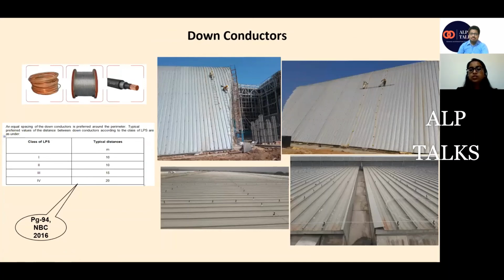Also, these holders and connectors are used at every 1 meter. If I am laying the down conductor through the wall, then at every 1 meter I need to put a holder or connector to hold the conductor over the roof, so that it is not in direct contact with my structure.